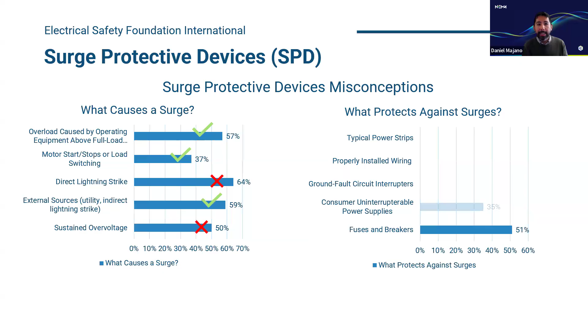And then when we asked them what causes a surge and what protects against a surge, we're not necessarily seeing that the education is there to understand it. You can see that a number of them on the left chart here said that sustained overvoltages and a direct lightning strike can cause a surge. On the right, we asked them what protects against a surge. Many of them said standard, typical power strips, properly installed wiring, ground fault devices, UPSs, and fuses and breakers can protect against surges. But surge protective devices protect against surges, not necessarily these devices. They can't protect against a sustained overvoltage that leads to a surge.